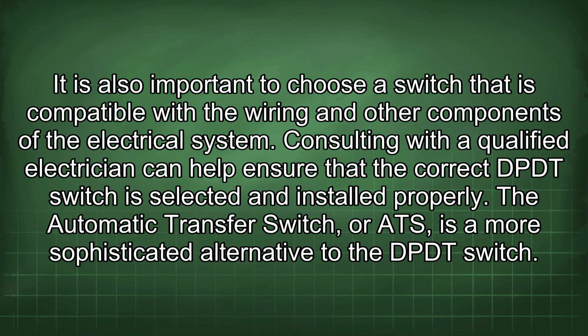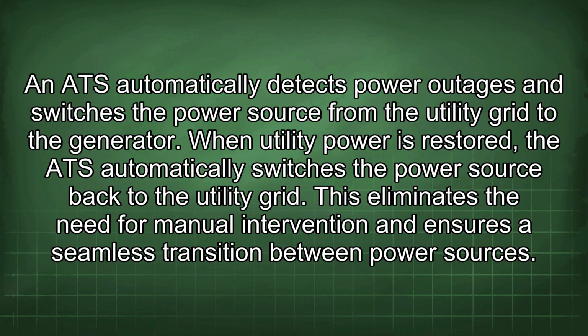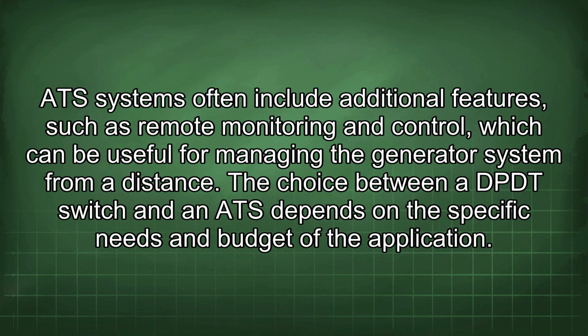The automatic transfer switch, or ATS, is a more sophisticated alternative to the DP-DT switch. An ATS automatically detects power outages and switches the power source from the utility grid to the generator. When utility power is restored, the ATS automatically switches the power source back to the utility grid. This eliminates the need for manual intervention and ensures a seamless transition between power sources.